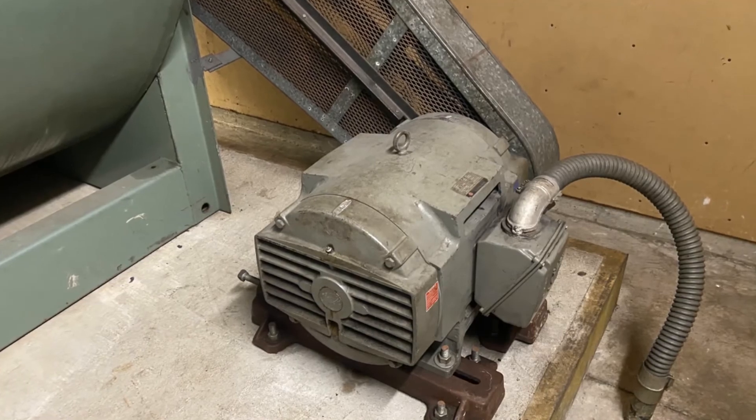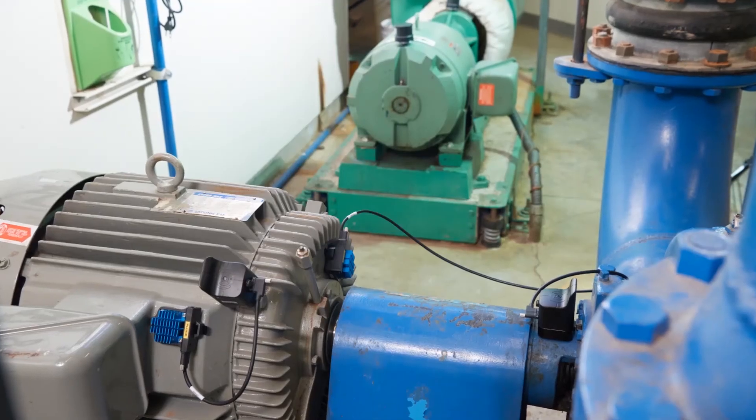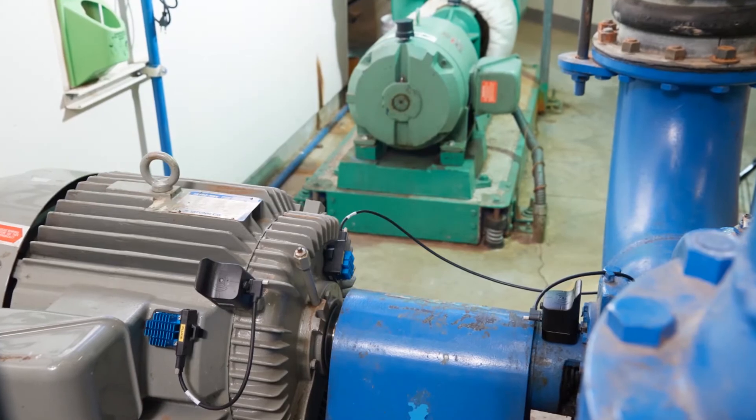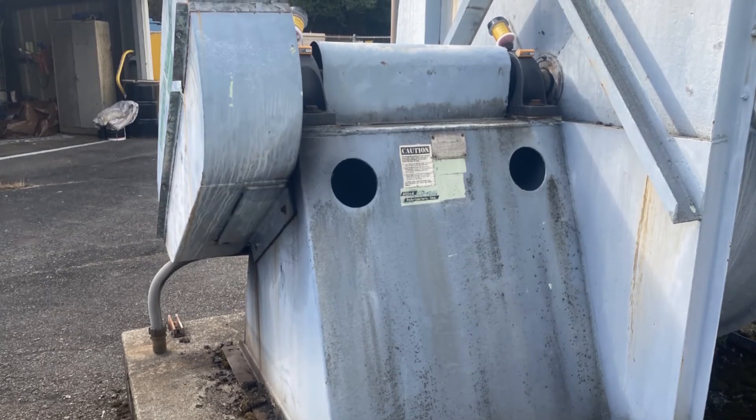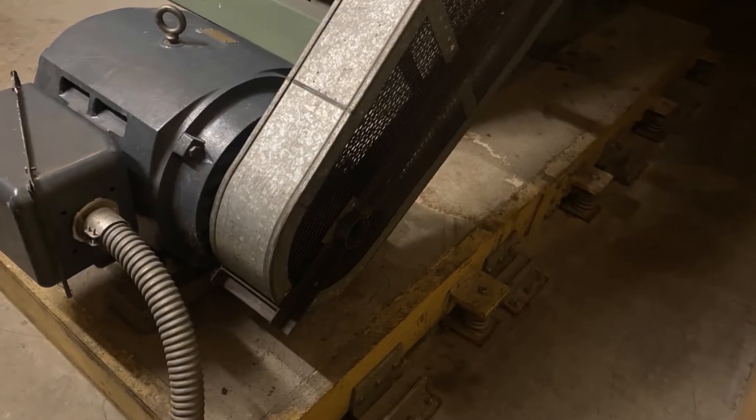High vibration could be from background noise, the process itself, an adjacent machine, the structure, or resonance. If users overreact and replace bearings just because it seems to be the fault most times, they will be disappointed.